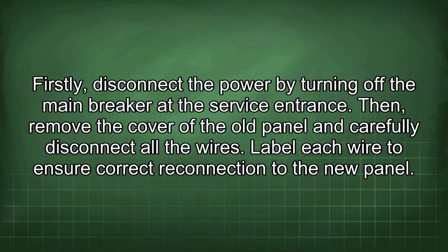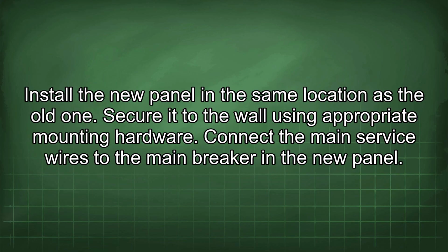Firstly, disconnect the power by turning off the main breaker at the service entrance. Then remove the cover of the old panel and carefully disconnect all the wires. Label each wire to ensure correct reconnection to the new panel. Install the new panel in the same location as the old one. Secure it to the wall using appropriate mounting hardware.